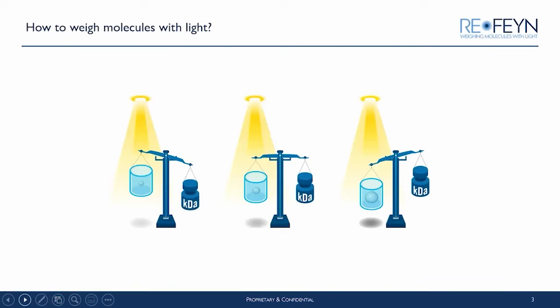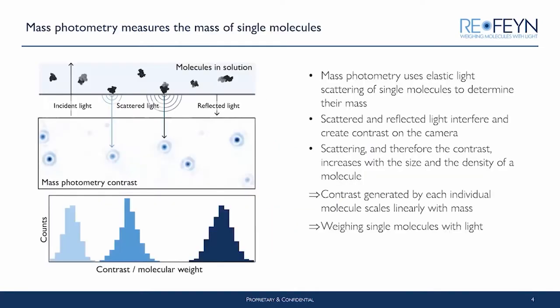So what is mass photometry? Essentially, it is using light to weigh molecules, and the working principle is very simple. All molecules scatter light and we can measure this scattering. Furthermore, molecules of different mass scatter light to different degrees — a small, lighter molecule will scatter less than a larger, heavier molecule. And it has been proven that there is a nice linear relationship between that signal and mass.